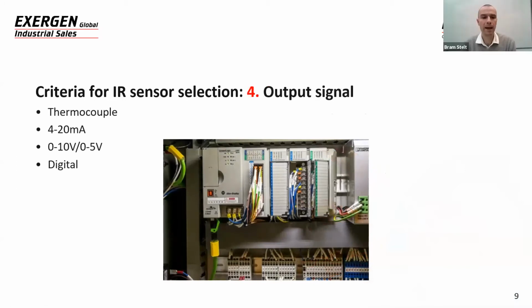Another criterion is the output signal. The IRTC line as we now have generates a thermocouple output signal. But of course, in the field, you see other output signals. It could be 4 to 20 milliamp, 0 to 10 volt, or 0 to 5 volt. Also, we see more and more demands for digital signals like I2C or I/O output. It really depends on what kind of system the customer has, and ideally, it should be kind of a plug-and-play principle. In general, the bigger machines tend to have a 4 to 20 milliamp or 0 to 10 analog output, because the signals run over bigger distances, so there is a bigger chance of electromagnetic interference.